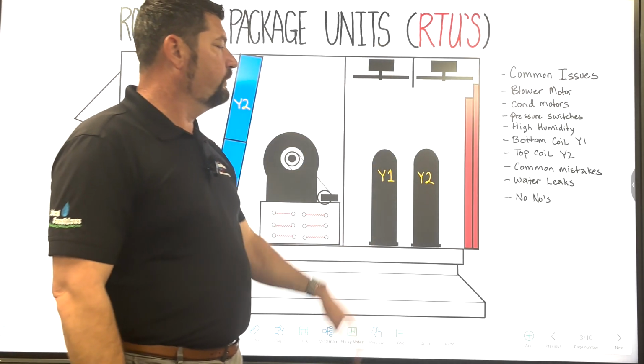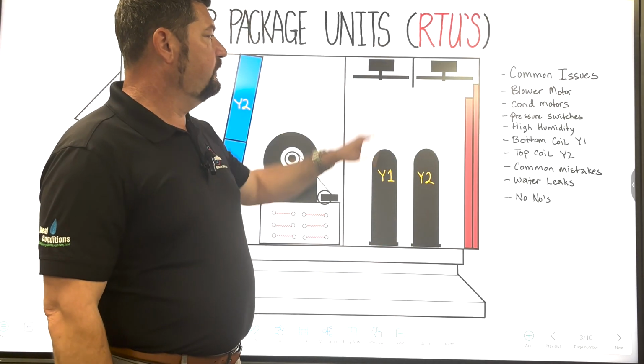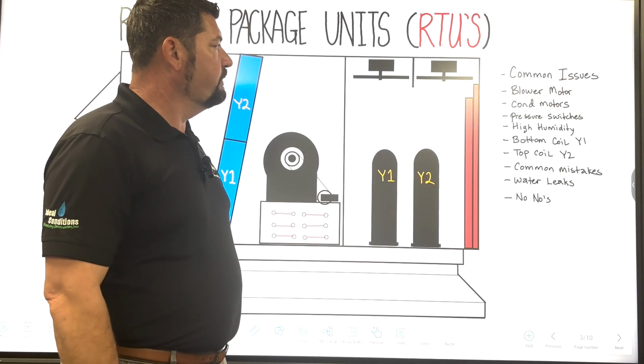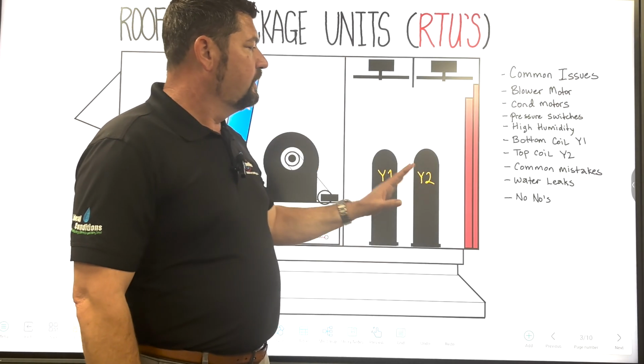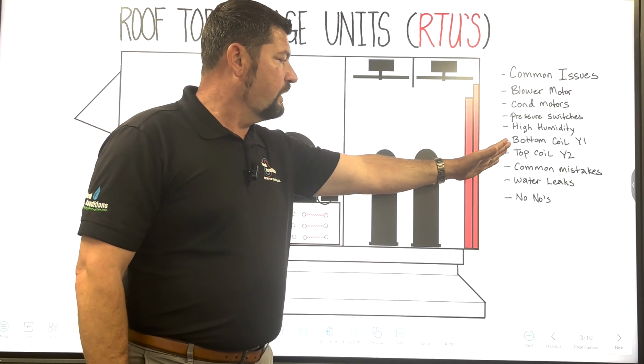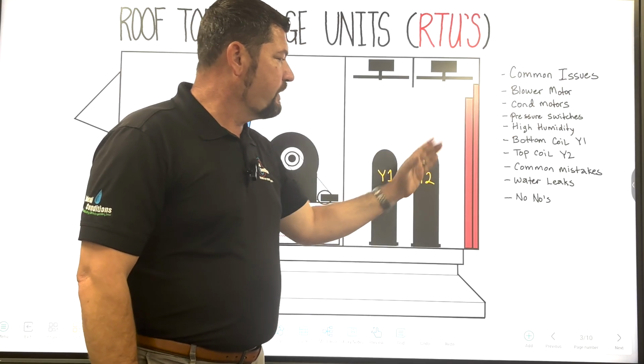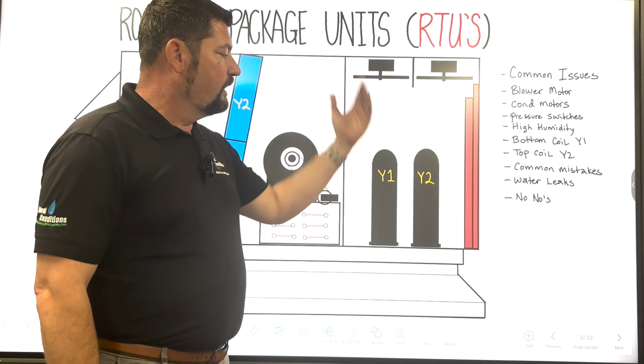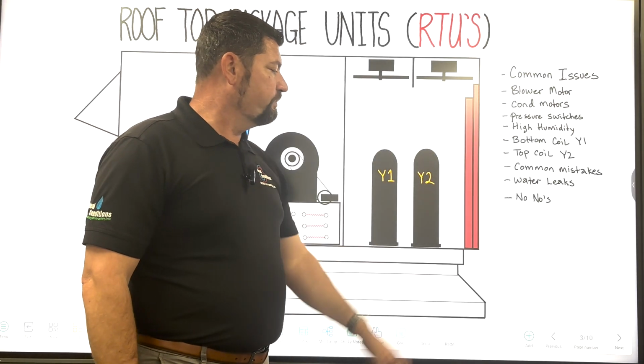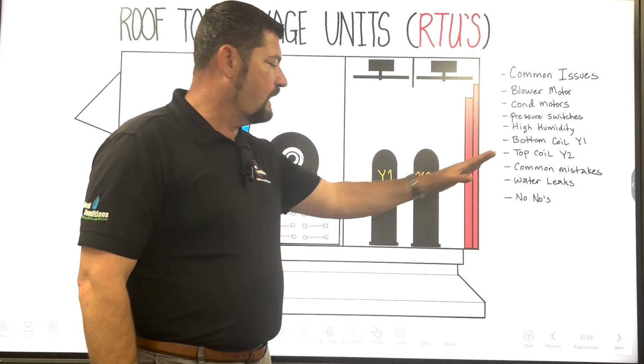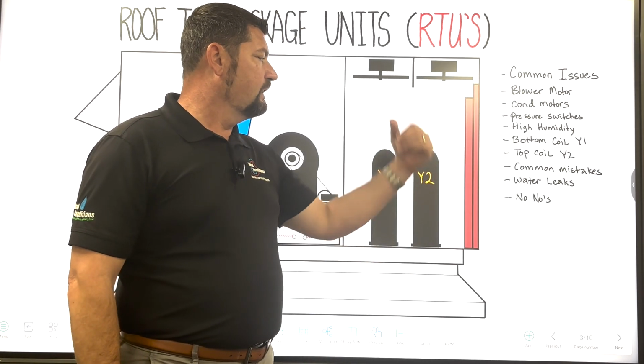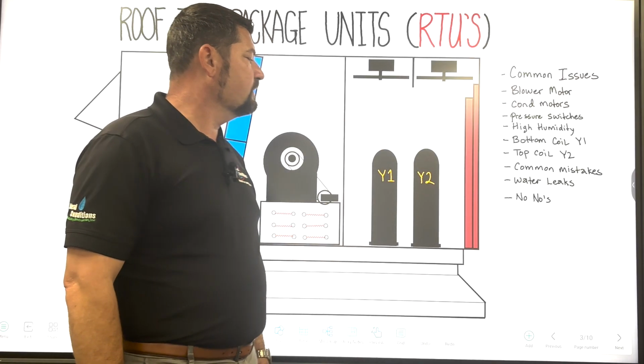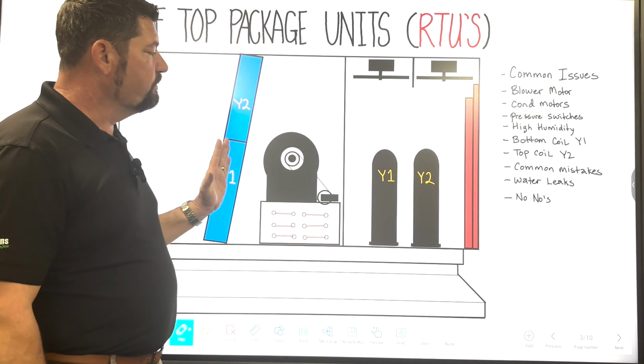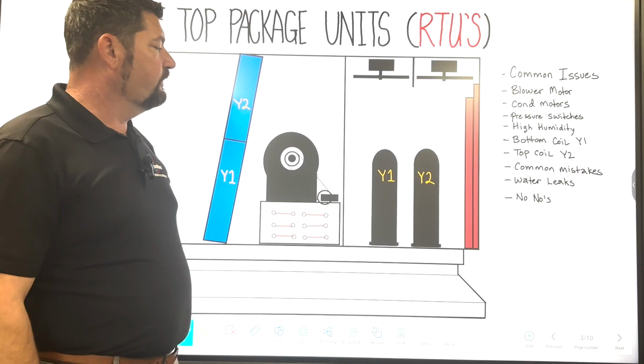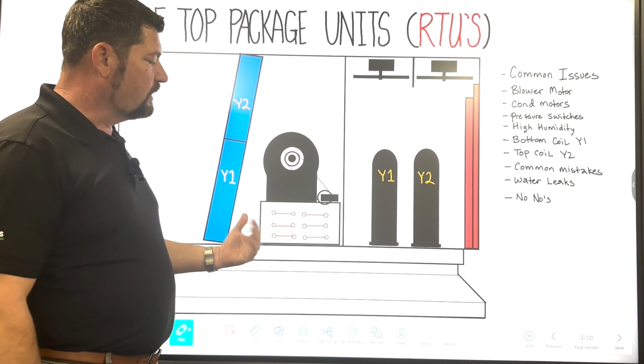Condenser fan motors that go out get replaced. They don't go back with the proper RPM and horsepower, so we don't turn at the proper RPMs and get that right amount of airflow. So we have pressures that are higher than they're supposed to be. That, in combination with the high heat index on the roof and the already high ambient temperatures in the summer, means these things just run pretty hard. They run pretty inefficiently, and they start causing problems.